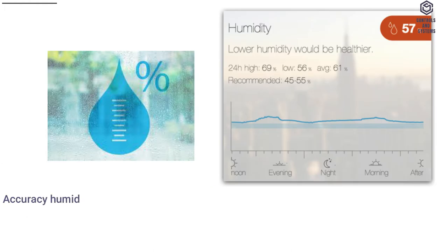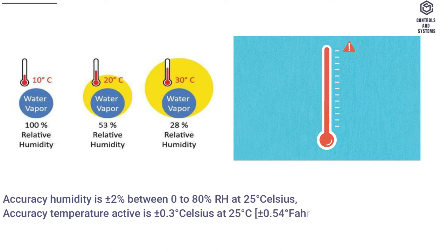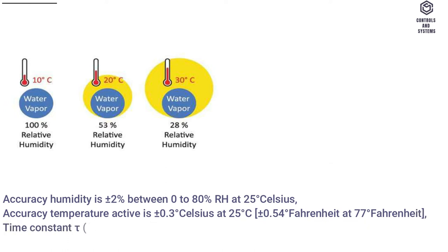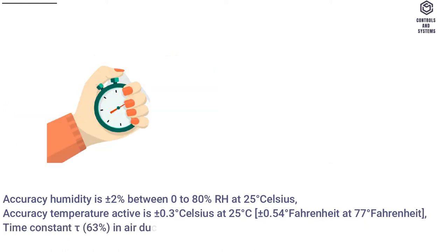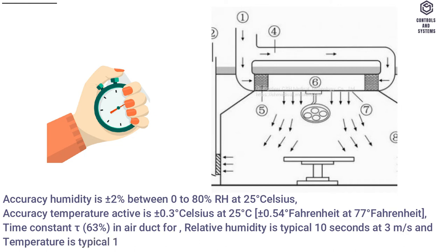Accuracy humidity is ±2% between 0 to 80% RH at 25°C. Accuracy temperature active is ±0.3°C at 25°C, or ±0.54°F at 77°F. Time constant at τ63%: in air duct, relative humidity is typically 10 seconds at 3 m/s, and temperature is typically 125 seconds at 3 m/s.